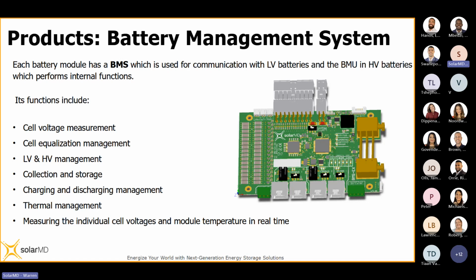The BMS is necessary with lithium iron phosphate batteries, as the lithium iron phosphate cells, of which there are 16 inside our batteries, need to be balanced. This wasn't necessary in older energy storage technologies like lead acid batteries. With lead acid batteries, balancing wasn't really too much of a concern. To use lead acid terminology, you'd refer to balancing as equalization. If you look at a standard 12-volt lead acid battery, there are 6 cells, 6 2-volt cells in series inside your average car battery, as an example.